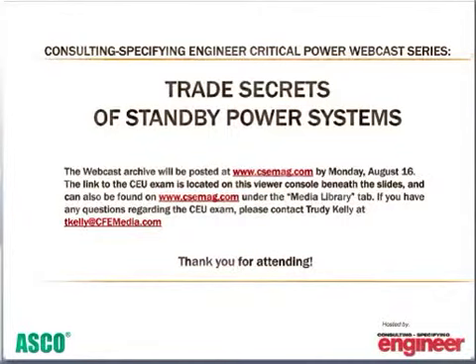Because it just goes back to the day tank. It returns, and really it ought to return to the main tank, because if it returns to the day tank and you get a lot of recycled fuel, the fuel temperature goes up. And if you've got a small day tank and a large generator, your fuel gets too hot. So it really should circulate back to the main tank. Okay. Very good. Thanks, Ken.